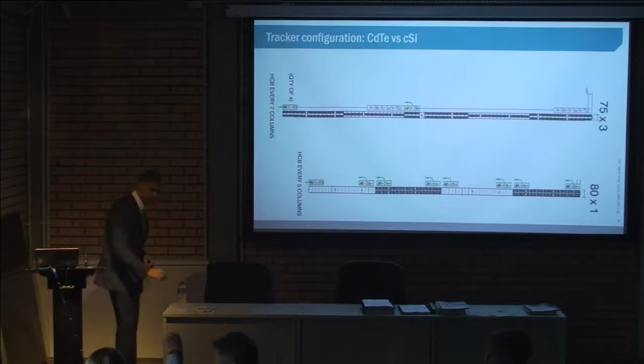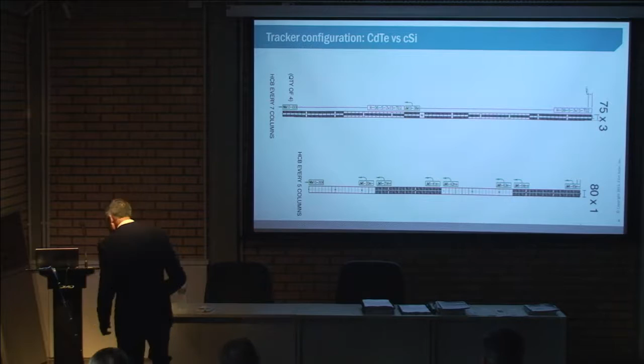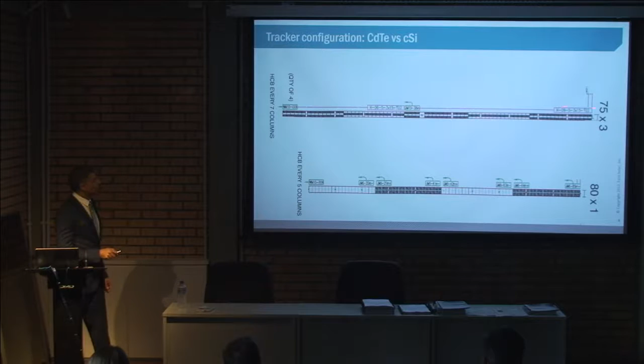Do you have a pointer here? Okay. So these boxes here and here represent the DC wiring for making the series connections. In this case, this is a harness where 9 strings are connected in parallel. So we have 9 strings of 15 modules connected to the harness. That means there are only 2 conductors coming out of that.